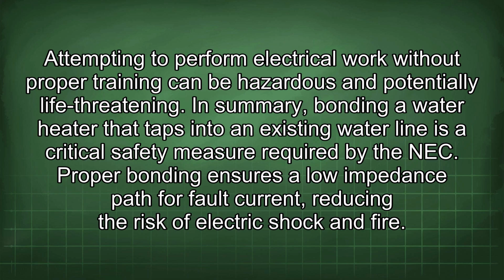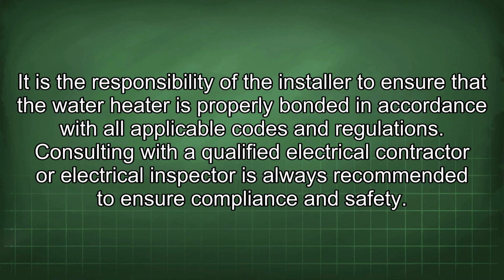In summary, bonding a water heater that taps into an existing water line is a critical safety measure required by the NEC. Proper bonding ensures a low impedance path for fault current, reducing the risk of electric shock and fire. It is the responsibility of the installer to ensure that the water heater is properly bonded in accordance with all applicable codes and regulations.